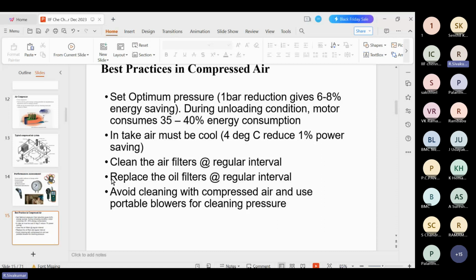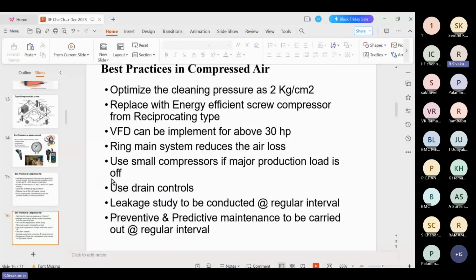And the second thing, as I discussed earlier, the air intake must be very cool. A 4 degree reduction will give 1% energy saving. So the compressor position, the room and the ambient environment should be maintained very clean. Clean the air filters at regular intervals. Similarly, replace the oil filters at regular intervals as per the OEM recommendations, avoid cleaning with compressed air, and use portable blowers wherever possible for cleaning purposes, optimizing the cleaning pressure to 2 kg per centimeter square. In every audit, we recommend that the cleaning pressure be maintained between 2 to 3 kg only.